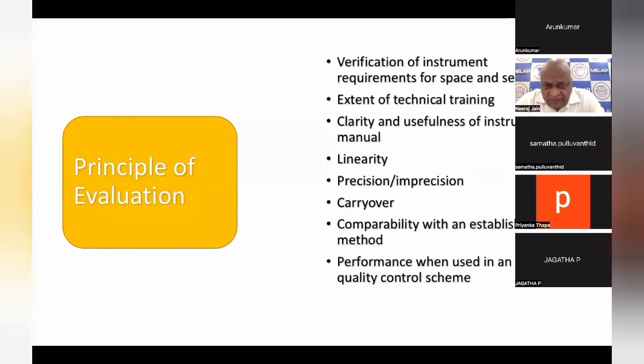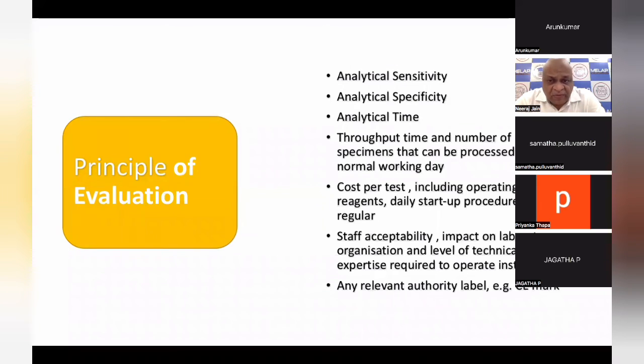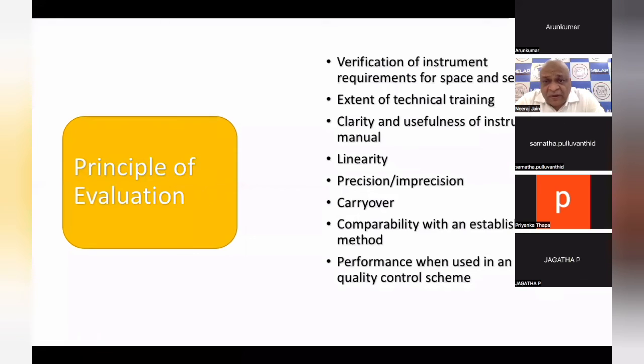And when you are evaluating a machine, when you are buying a machine, what is required? First of all, ask company people to come and approve your space, whether this space is adequate or not. There is no excess dust, lighting is okay, temperature, etc. All these things are well maintained. Now, how much training is required, whether the operation manual has clarity or not. You're also checking linearity of various parameters, whatever specifications they are telling you, what is the precision, how much variation is there. You can say within run, between run, carry over. A low value sample is not affected by a previously run high value sample. When you are participating in a quality control scheme, external quality control, what is the performance of that equipment?